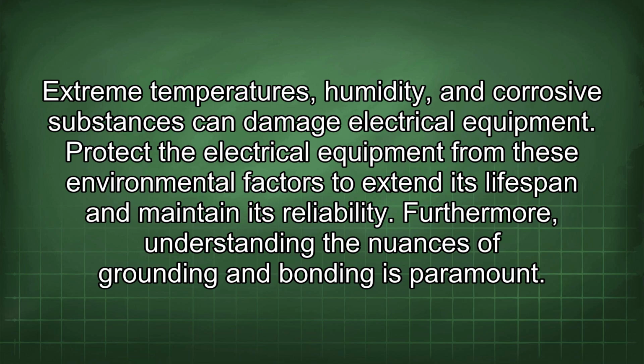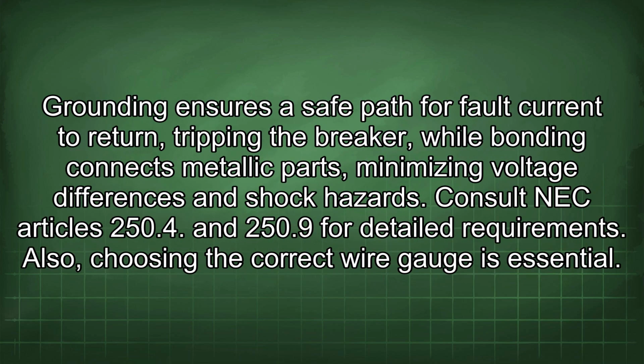Furthermore, understanding the nuances of grounding and bonding is paramount. Grounding ensures a safe path for fault current to return, tripping the breaker, while bonding connects metallic parts, minimizing voltage differences and shock hazards. Consult NEC Articles 250.4 and 250.9 for detailed requirements.